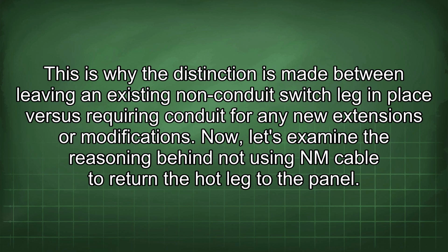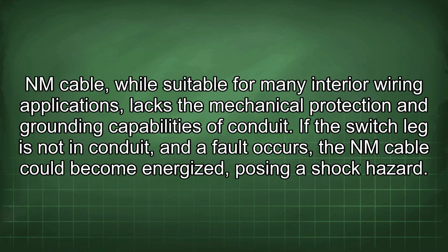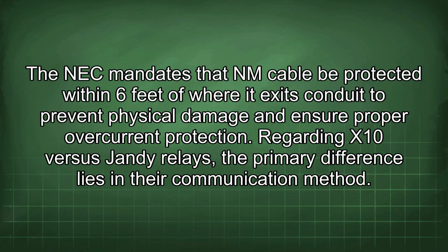Now, let's examine the reasoning behind not using NM cable to return the hot leg to the panel. NM cable, while suitable for many interior wiring applications, lacks the mechanical protection and grounding capabilities of conduit. If the switch leg is not in conduit and a fault occurs, the NM cable could become energized, posing a shock hazard. The NEC mandates that NM cable be protected within 6 feet of where it exits conduit to prevent physical damage and ensure proper overcurrent protection.